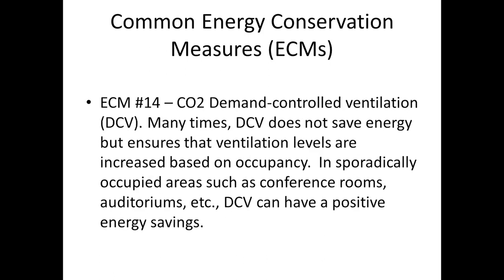CO2 demand controlled ventilation. Many times this allows us to accurately bring in more fresh air for a building, and it doesn't necessarily have an impact on energy efficiency, but in areas like conference rooms, auditoriums, gymnasiums, where occupancy is sporadic, it can allow us to drop down ventilation level to a minimum and have energy savings.